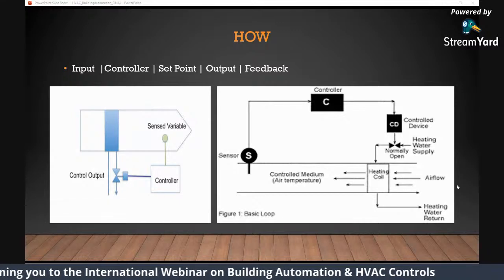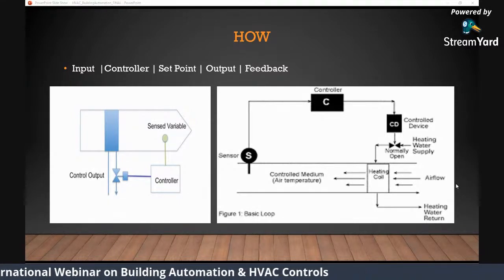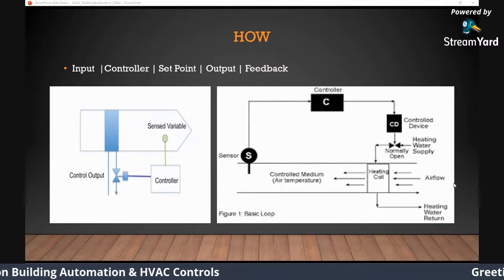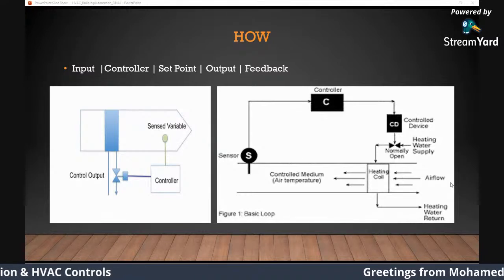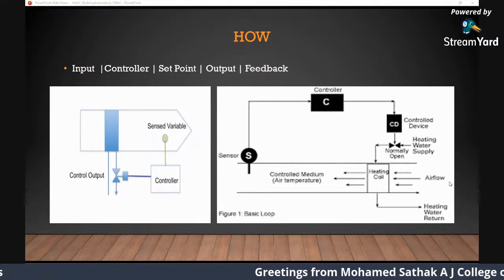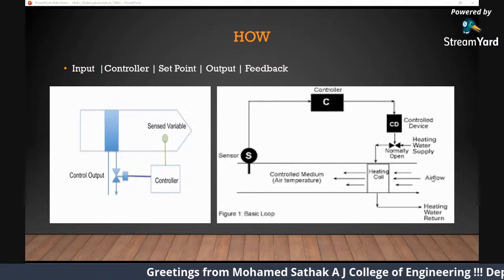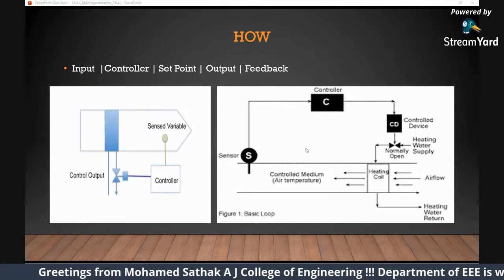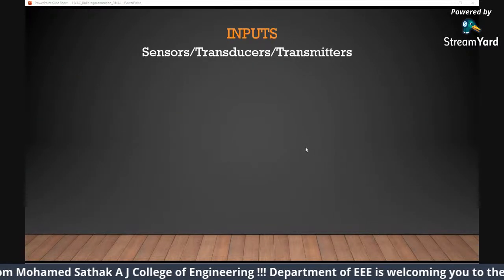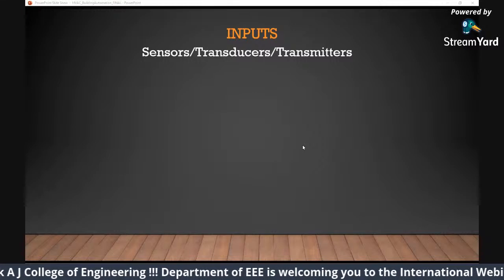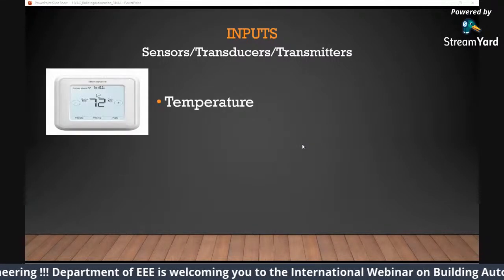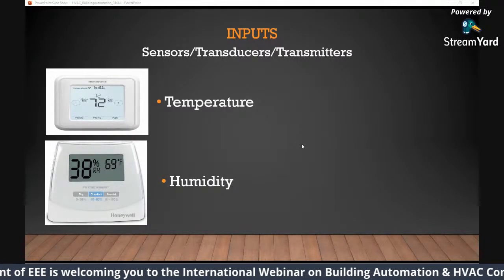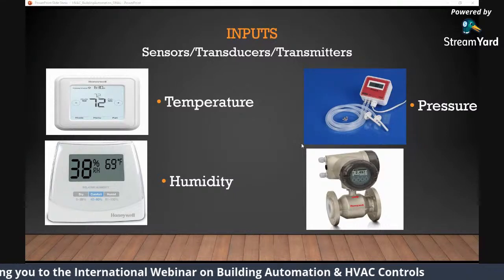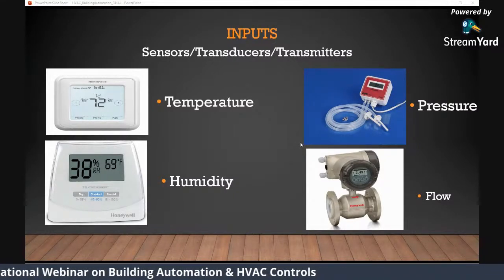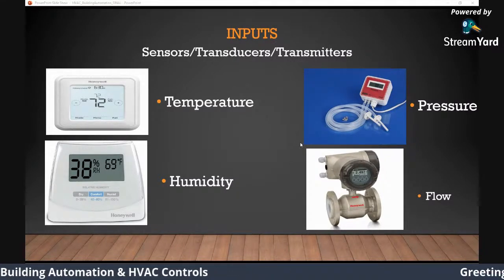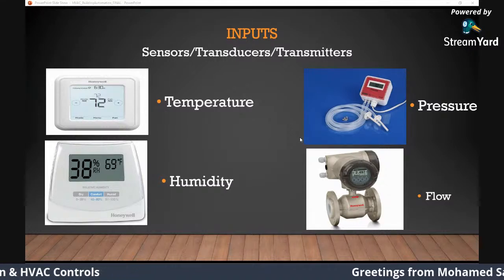Okay, great. So this is your old concept or your principle which operates on your HVAC building automation system. Three parameters: sensed variable, control output, controller, and it controls every other parameter or variable in the HVAC field. So what are the different types of inputs we come across? As I mentioned earlier, we have temperature, we have humidity, we have pressure, we have flow. We don't deal with pressure or flow in our day-to-day life, but temperature and humidity you should have heard about.